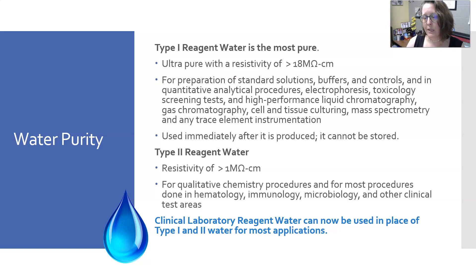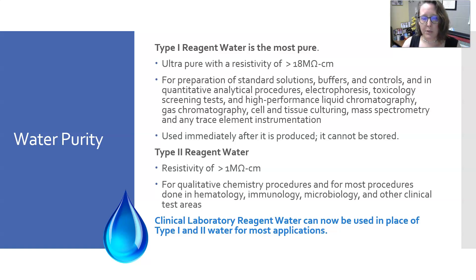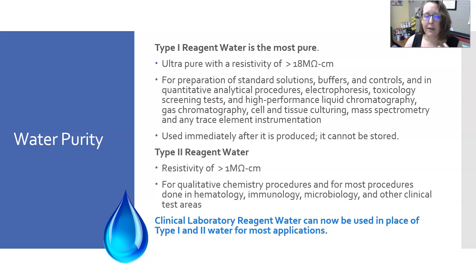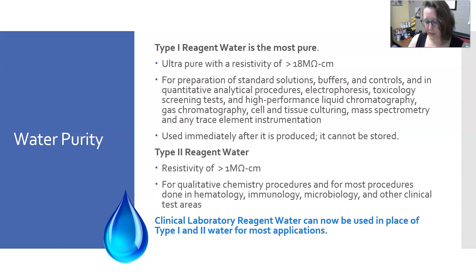Usually, instruments that need Type 1 water have a feed that supplies the analyzer directly so it can use the ultra-pure reagent water. Type 2 reagent water requires a resistivity of greater than 1 mega-ohm per centimeter. It is used for qualitative chemistry procedures and for most procedures done in hematology, immunology, microbiology, and other clinical test areas. Clinical laboratory reagent water can now be used in place of Type 1 and Type 2 water for most applications.